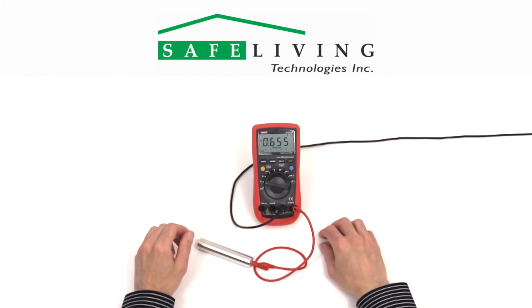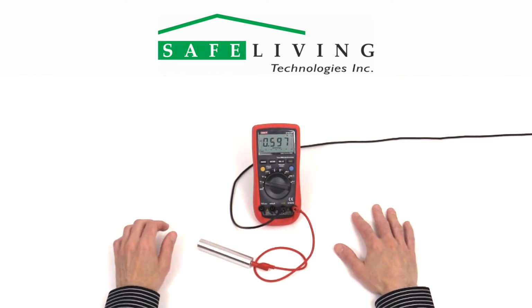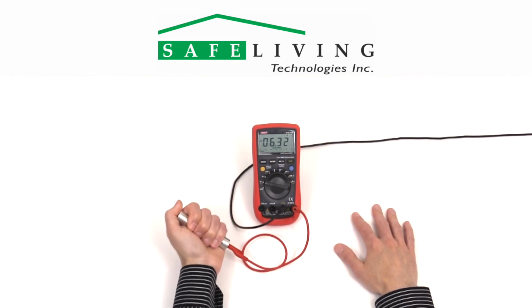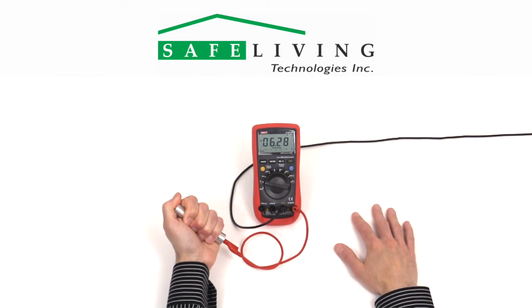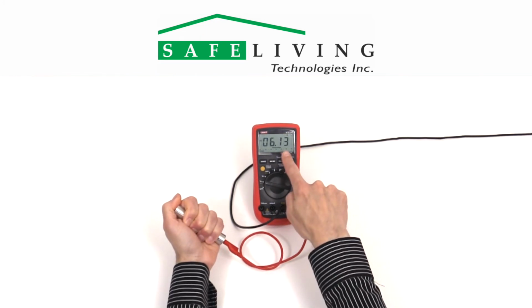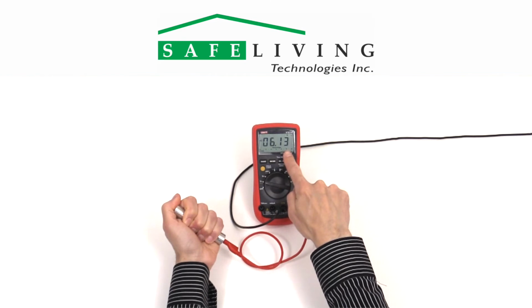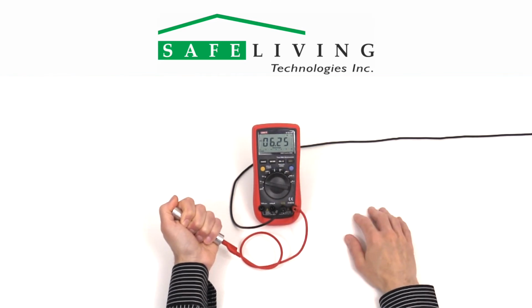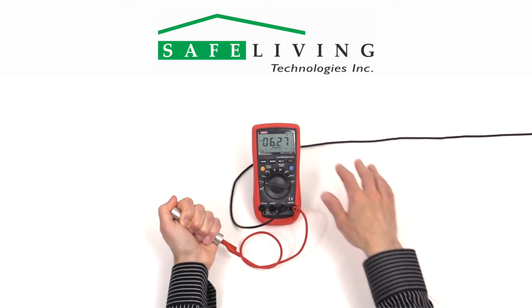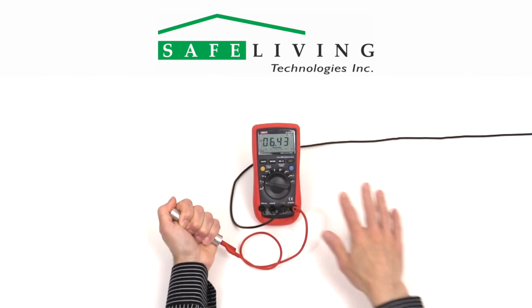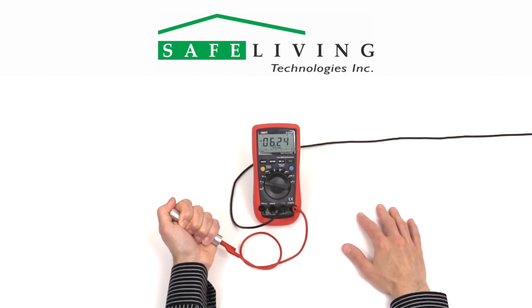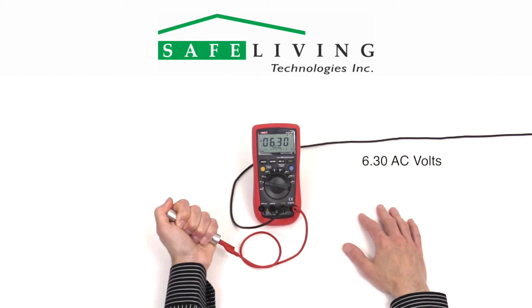Sit or lie in the position that you wish to measure while gripping the hand probe snugly in one hand as shown. Record the meter's reading. Note that other people in the area can influence this reading, so they should remain at least 5 feet away during the measurement. And while measuring, do not touch any other conductive area that could have a ground connection. Also, make sure your feet are not touching the ground or floor if you're sitting. Note the measurement on the display is shown in AC volts. Simply multiply this reading by 1000 for the value in millivolts.